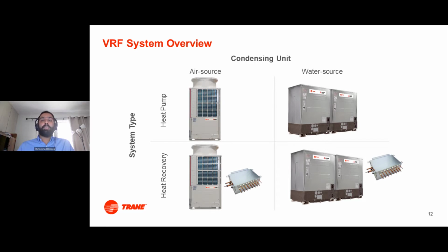It also allows the system to direct refrigerant into the different zones that it's needed and allow thermal exchange between different zones in the building. An additional quality that I would like to mention is that while air source systems are more popular within the industry, water source systems are becoming increasingly popular, and we also have heat recovery available within water source systems. They're a great choice for geothermal applications, maybe campuses with existing condenser loops, and if you have large water source heat pump replacements, just to name a few applications.